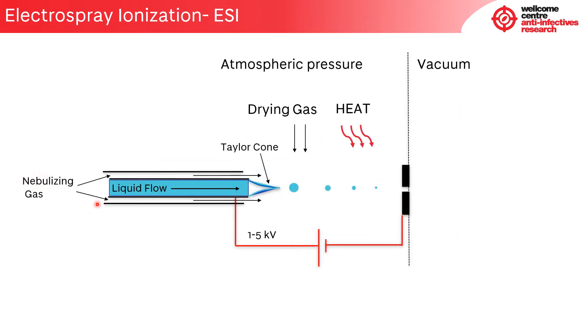In addition to the nebulizing gas, most electrospray sources also use an additional drying gas to help with solvent evaporation and heat the entire source block area for the same reason. This can be problematic for thermally labile compounds, but it does allow high flow rates of half a millilitre to a millilitre per minute to be used without requiring the flow to be split before entering the mass spectrometer.